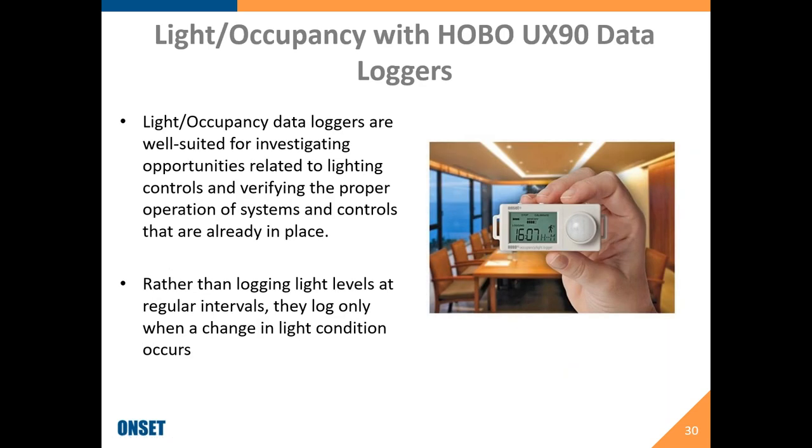So we're going to talk a little bit more about the light and occupancy loggers, the UX90s that we spoke about a few moments ago. They're really well suited for investigating opportunities related to lighting controls and verifying proper controls of systems. Rather than logging at regular intervals, which is common with some of our loggers in general, these will only log when there's a change in the state value that it's looking at. That conserves battery to a certain extent, and it gives you better information.